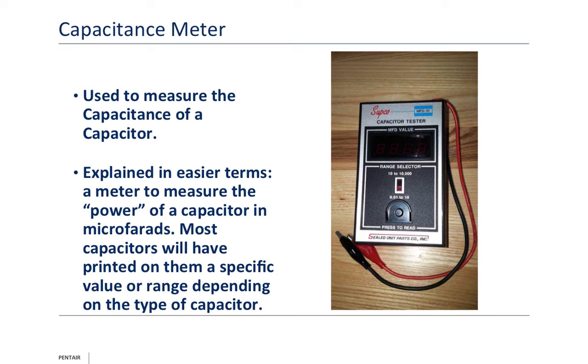The key also to remember is with the black or dark brown start capacitors, those have a range of, say, 86 microfarad plus 20 minus 0. You can't go below the minimum microfarad, which is 86 in our example. So always check your capacitor. You can't go below, but you can always go above, up to 20%. Run capacitors, the silver ones, are often, say, 35 microfarad plus or minus 5%. So read to know what number you're looking for. You might have to do a little math.